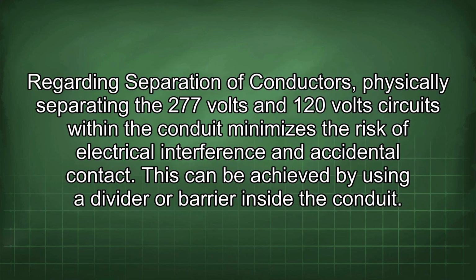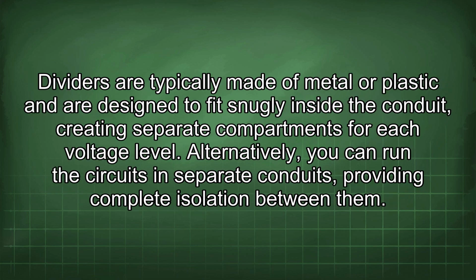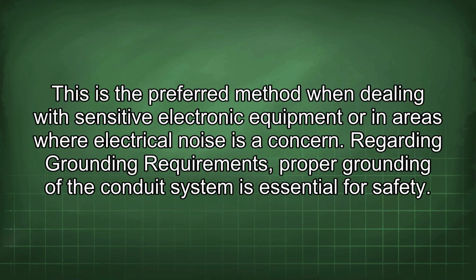Regarding separation of conductors, physically separating the 277 volt and 120 volt circuits within the conduit minimizes the risk of electrical interference and accidental contact. This can be achieved by using a divider or barrier inside the conduit. Dividers are typically made of metal or plastic and are designed to fit snugly inside the conduit, creating separate compartments for each voltage level. Alternatively, you can run the circuits in separate conduits, providing complete isolation between them. This is the preferred method when dealing with sensitive electronic equipment or in areas where electrical noise is a concern.